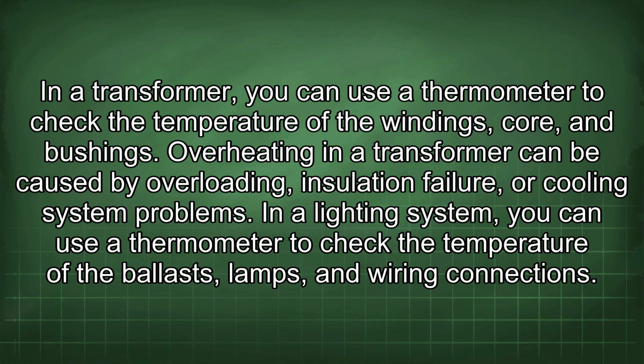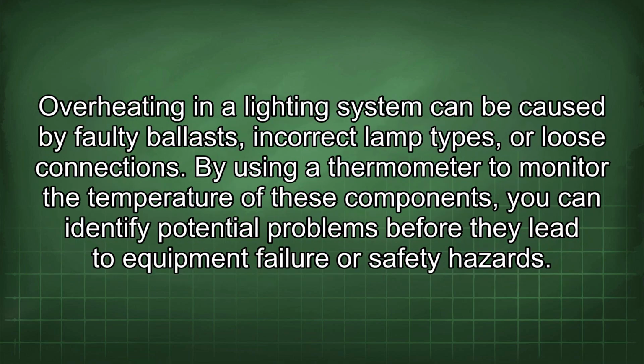In a transformer, you can use a thermometer to check the temperature of the windings, core, and bushings. Overheating in a transformer can be caused by overloading, insulation failure, or cooling system problems. In a lighting system, you can use a thermometer to check the temperature of the ballast, lamps, and wiring connections. Overheating in a lighting system can be caused by faulty ballasts, incorrect lamp types, or loose connections. By using a thermometer to monitor the temperature of these components, you can identify potential problems before they lead to equipment failure or safety hazards.